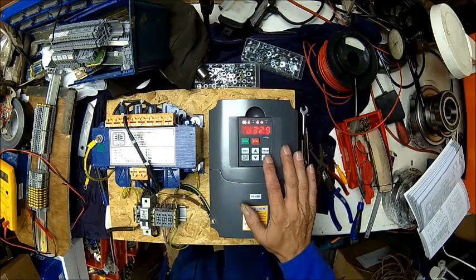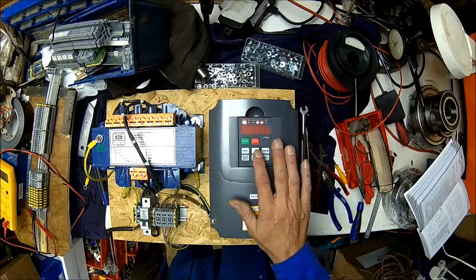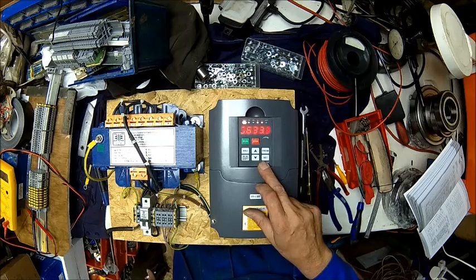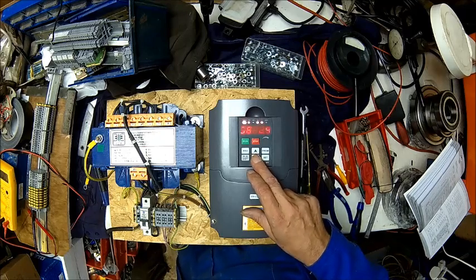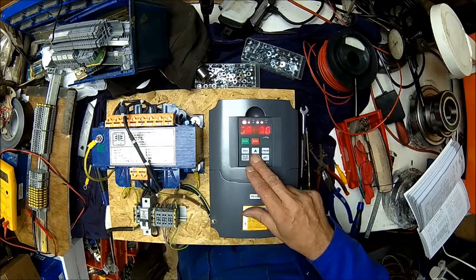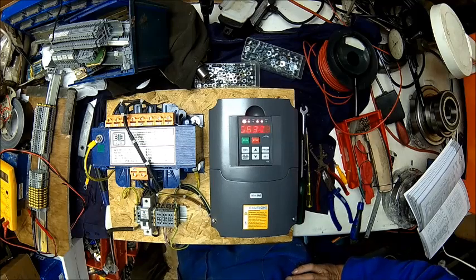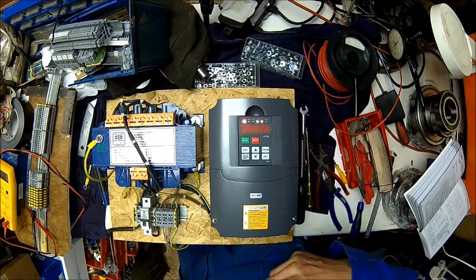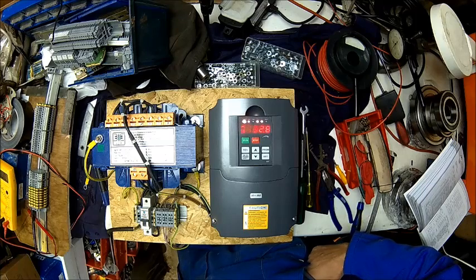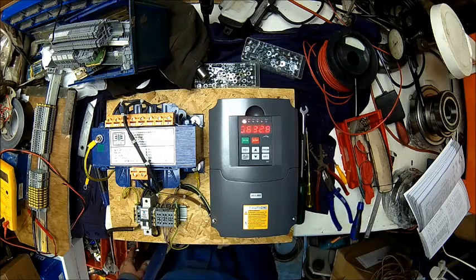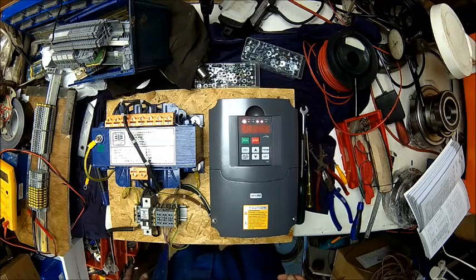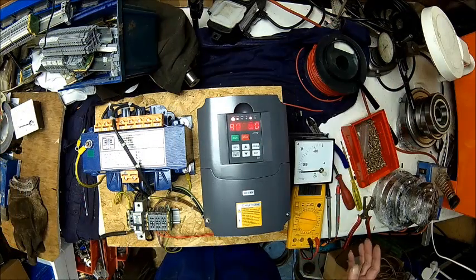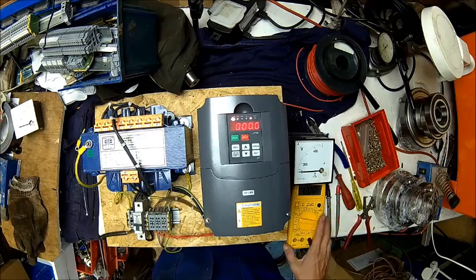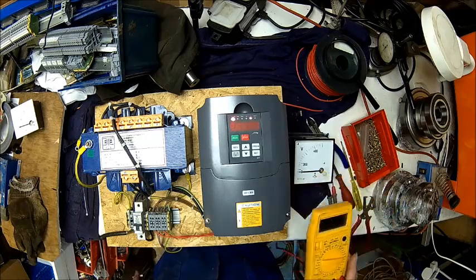A little idler motor will probably help to get the spikes down a little bit, especially if you run an old motor. I would recommend to crank the motor voltage down a little bit to 405 or 400 volts, depending what's on the nameplate. If you go 5% lower, it does help to increase the life of your motor, because these high voltage spikes are not good for your insulation if you got an old motor. So you rather want a little bit lower, or proper filtering on the output. It's your choice.